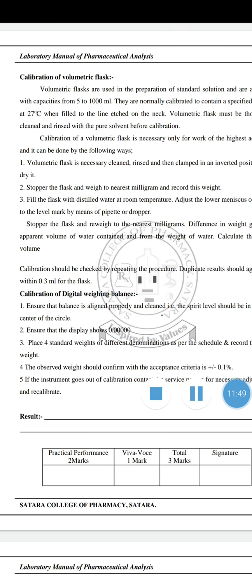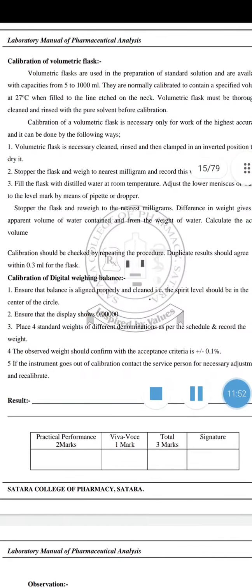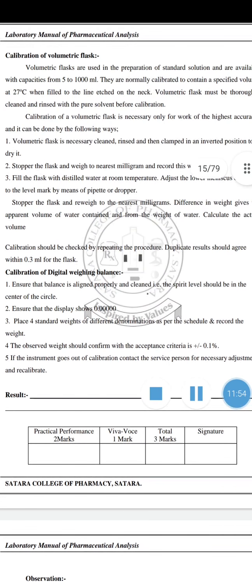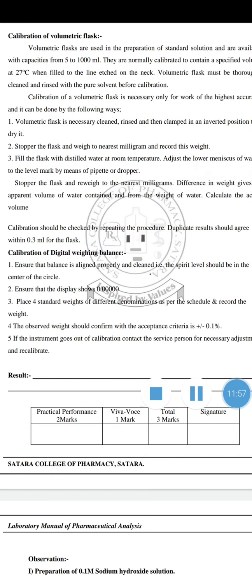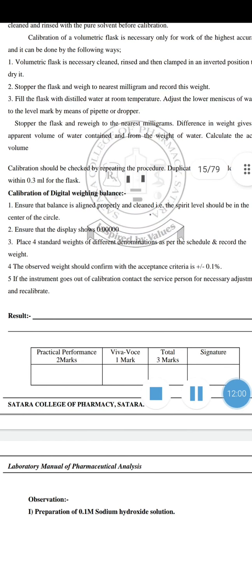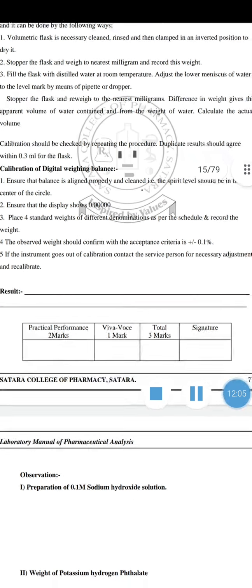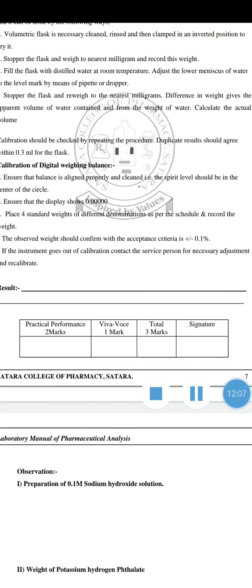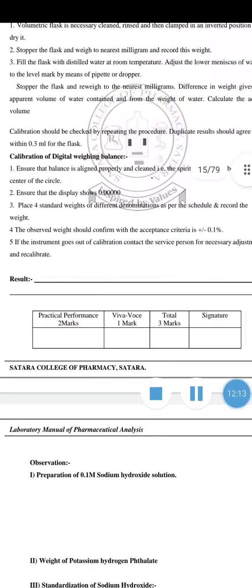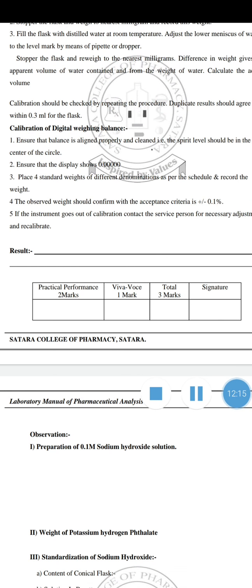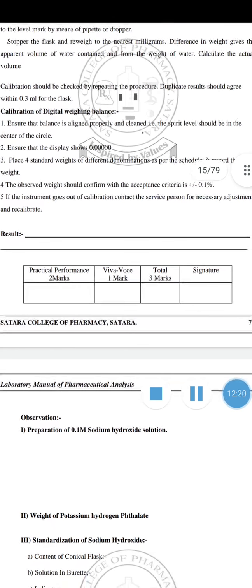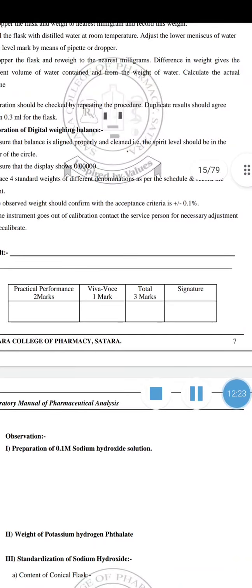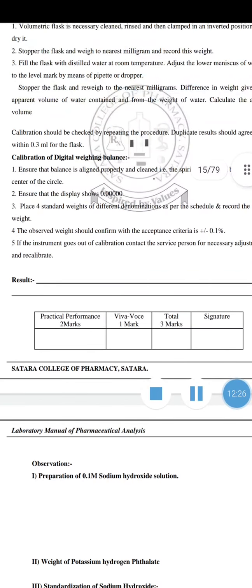Then calibration of a digital weighing balance: ensure the balance is aligned properly and clean, that is, the spirit level should be in the center of the circle. Then ensure the display shows 0.00. Then place 4 standard weights of different denominations as per the schedule and record the weight. Then observe that the weight should conform to the acceptance criteria of plus or minus 0.1%, and if the instrument goes out of calibration, contact the service person for necessary adjustment and recalibrate.